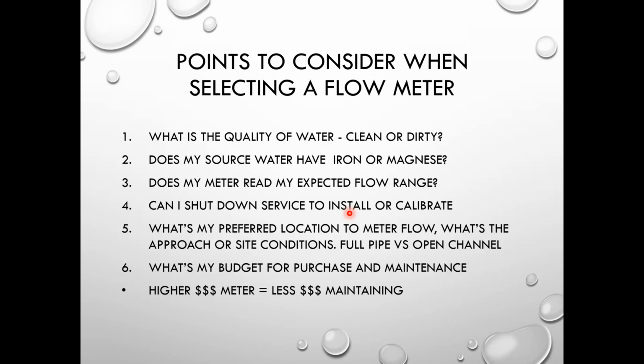If I'm using my Floatar sensor, what we do a lot of times is we find a place where they want to monitor the flow and put in a monitoring manhole. So they'll excavate down to the pipe, they'll cut a window over the top of the pipe. They then will put a cone section over the top of the pipe, and then they'll pour concrete as a base, right, and slope it towards the cut. They call that a pour-in-place base for the manhole, and they can install those while keeping the line in service. And it keeps the flow basically in the pipe, and you don't have any difference in roughness when it goes from pipe to manhole channel back into a pipe, right? So it keeps that same roughness coefficient through the monitoring process.